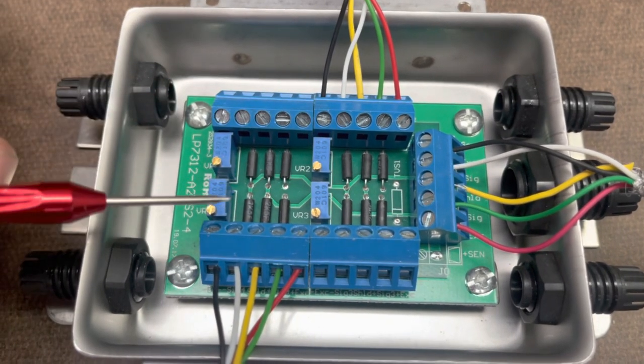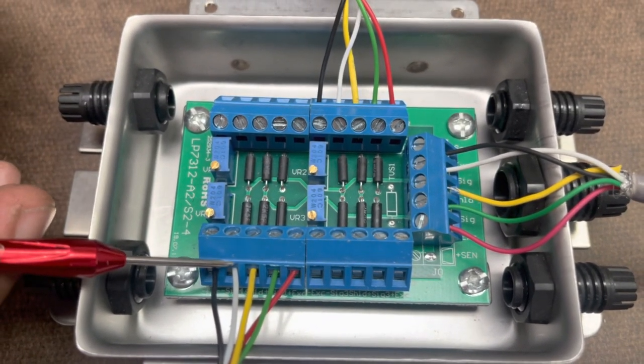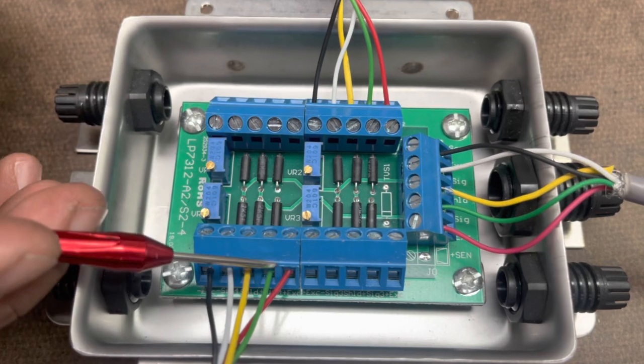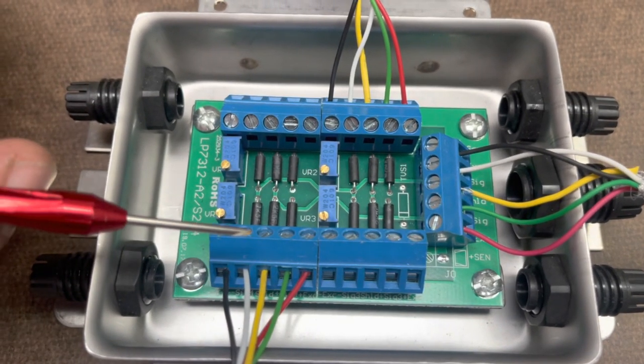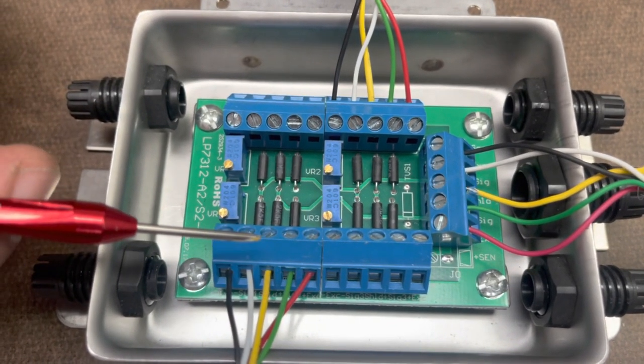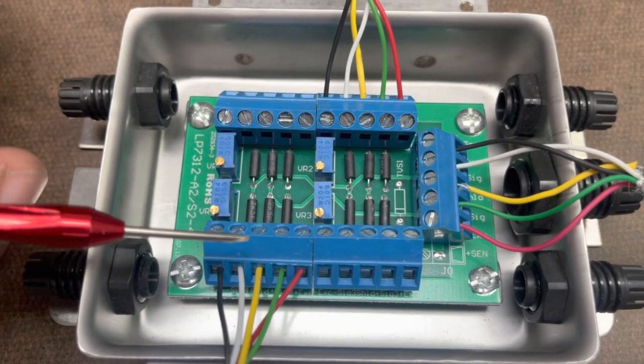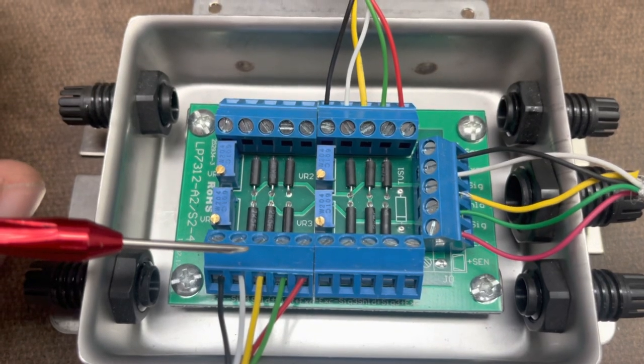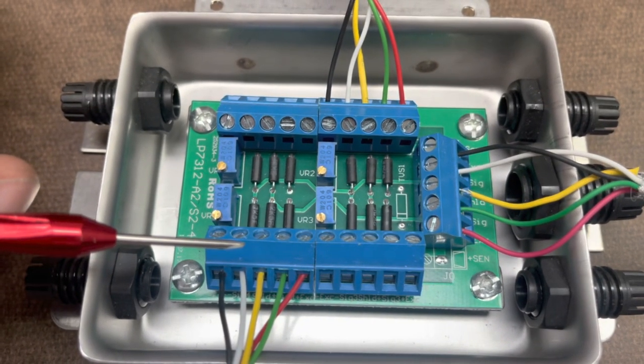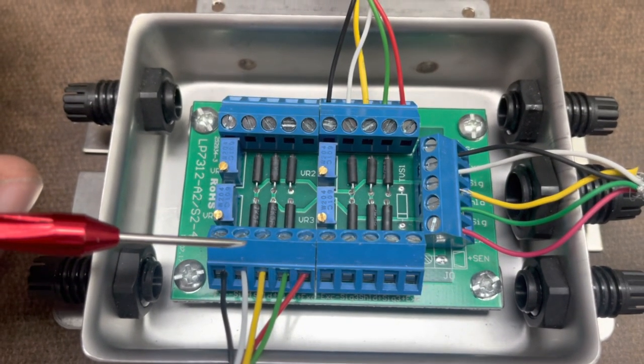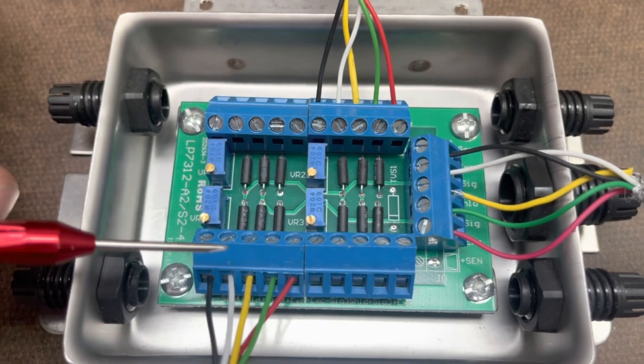two, three, and four. What you have to do is switch the white one with the green one, and that would reverse the load cell resistance direction. Basically it would flip it without you actually having to take it out of the scale and reinstall it.